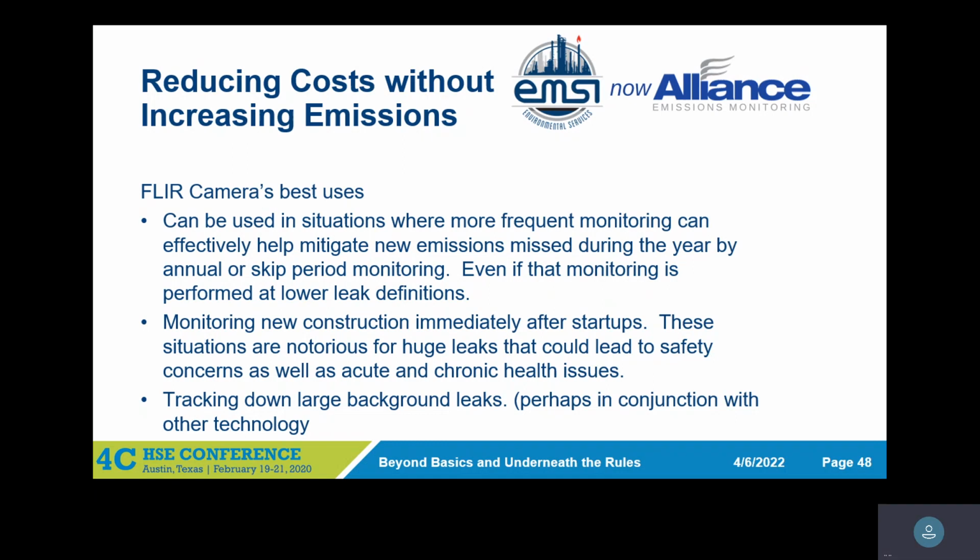Yeah, as you mentioned, the 10 to 15 mile an hour winds, remember that curve that goes throughout the day. So chances are, if you're doing a survey, you'll find more leaks in the morning when the wind is calm versus in the afternoon, when the sun plays a big factor. If it's a cloudy day, you have a better chance. But with the sun and the shadows and the wind kicking up, it becomes very difficult to find those leaks later in the afternoon with the FLIR camera.